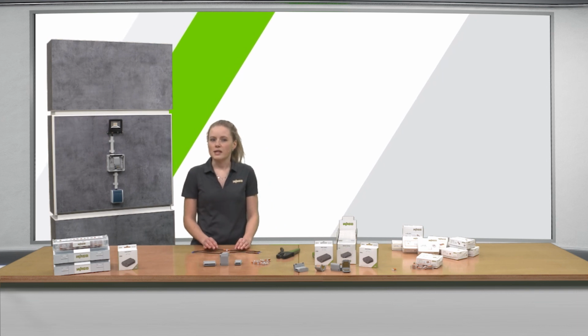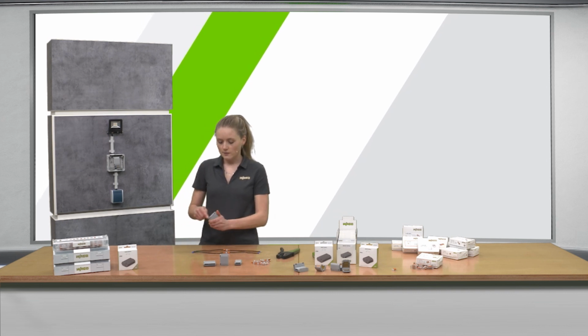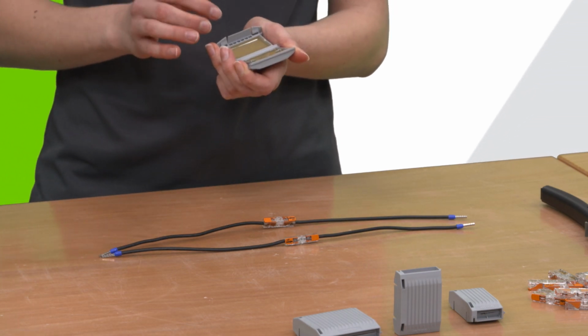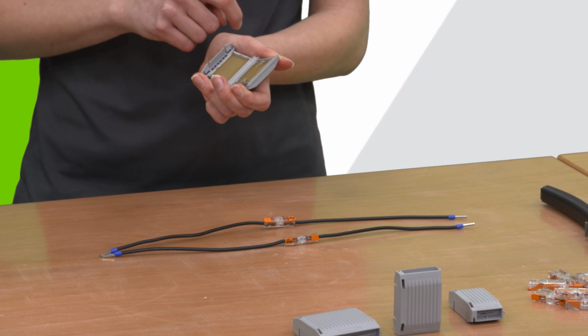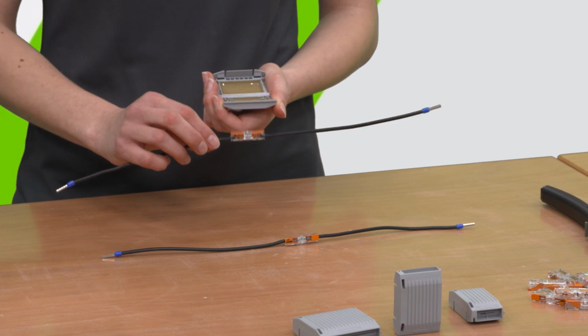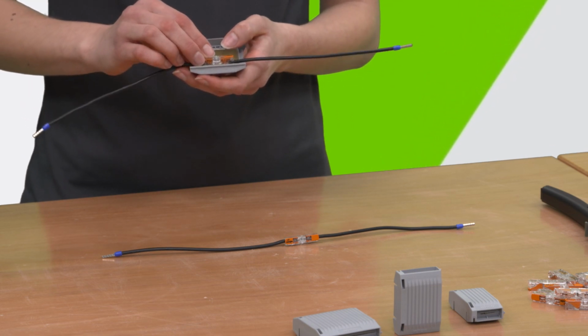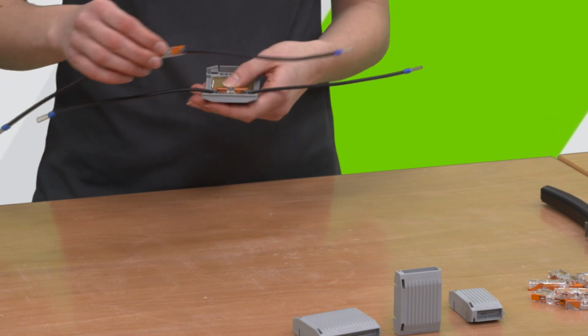How do I use the Gelbox now? I open the Gelbox at the side tabs. There are 2 trays pre-filled with silicone-free polyurethane gel. In one tray you can see a T-bar, and this T-bar helps us for positioning the connector. Now I put the previously wired connector in the Gelbox and press it onto the gel mass, so it sticks directly on the gel mass.